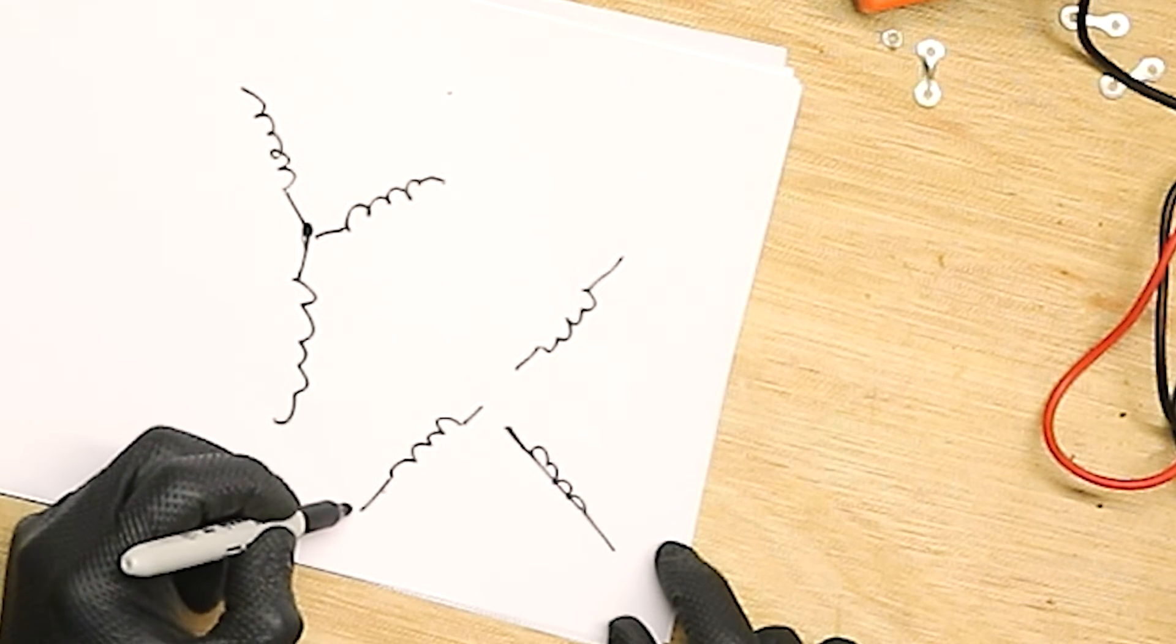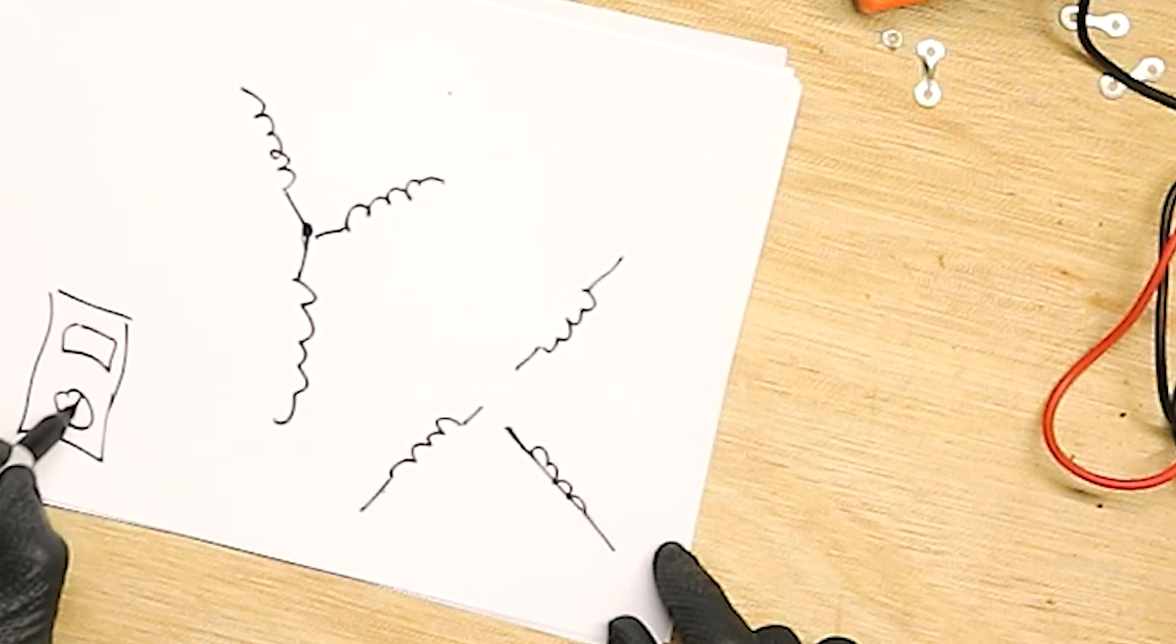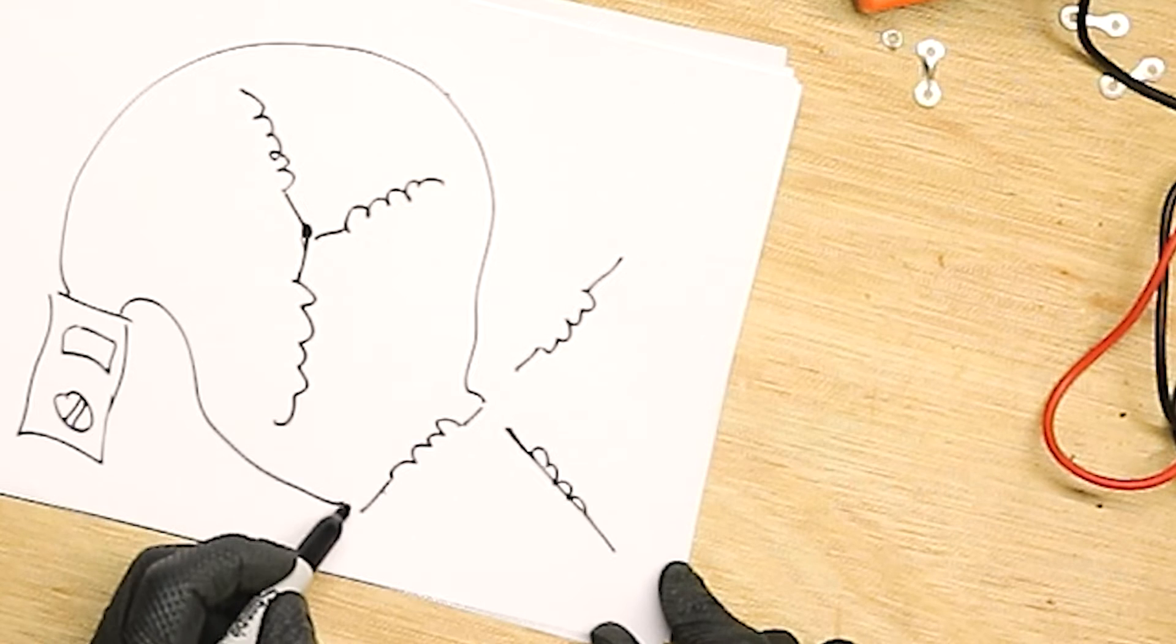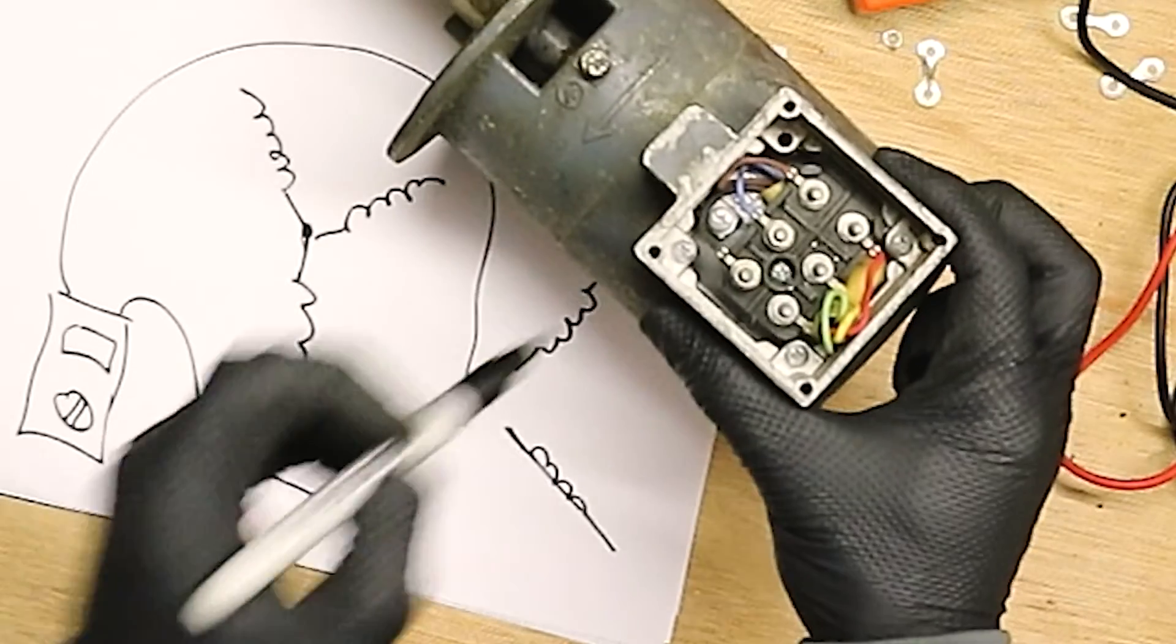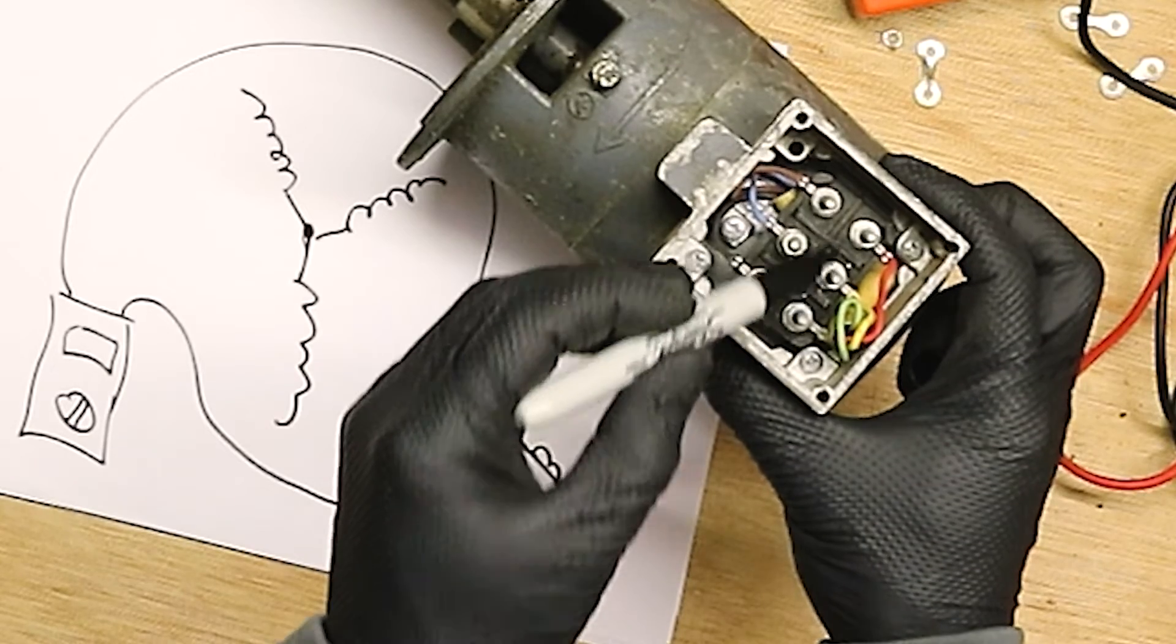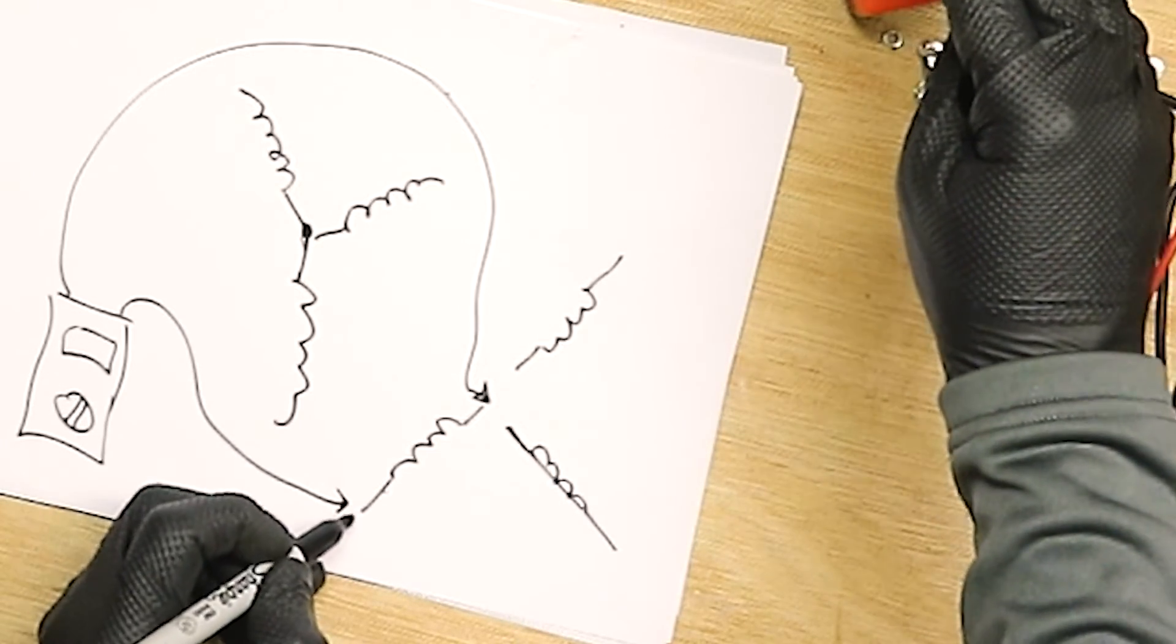We've tested with our meter to there, to there, and to that point, to check continuity between here and here, which is this wire and this wire. If we're at U2, that's the beginning of our winding here, and our end of our winding there, which is wound through the motor. We've checked there and there, and there's no continuity.